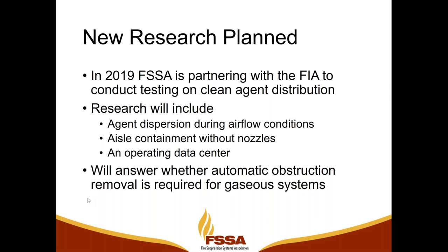The FSSA has been able to acquire a facility that's built as a data center to do this testing. And the hope is that the testing will answer whether or not automatic obstruction removal is required for gaseous systems. We are sure from a practical standpoint, it will still be required for sprinkler systems, but if there is a gaseous system in play, will those obstructions need to be removed, or will the gas flow through the equipment and build concentration in the contained aisleway? So just look forward to more communications from the FSSA on the results of that testing. Depending on what is learned, I'm sure some of that information will make its way into NFPA 75 and 76 and maybe NFPA 2001.